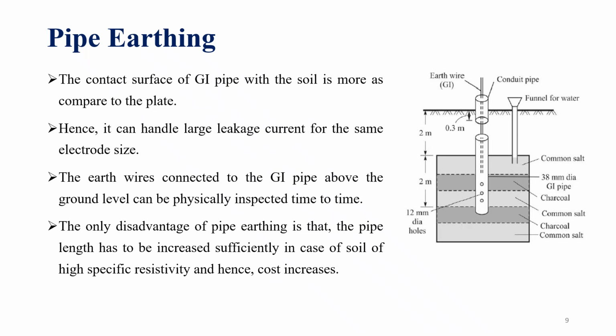The contact surface of the GI pipe with the soil is more compared to the plate. As compared to the plate earthing method, the electrode contact area with the earth is going to be more here, so that more current can be passed. So this type of earthing can handle large leakage current as the contact surface area is more, and the earth wire is connected to the GI pipe above the ground level. We already explained that in the previous slide. So the earth wire is connected to the electrode above the ground level, so that we can periodically check whether the connection is broken or not.